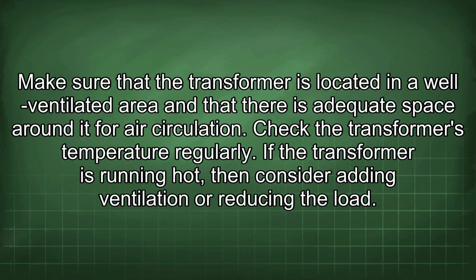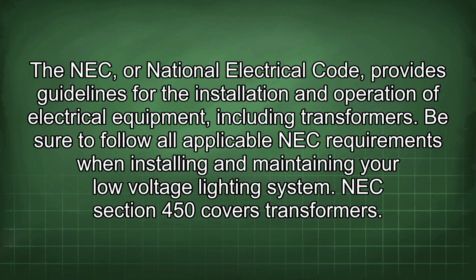Make sure that the transformer is located in a well-ventilated area and that there is adequate space around it for air circulation. Check the transformer's temperature regularly. If the transformer is running hot, then consider adding ventilation or reducing the load. The NEC, or National Electrical Code, provides guidelines for the installation and operation of electrical equipment, including transformers. Be sure to follow all applicable NEC requirements when installing and maintaining your low-voltage lighting system.